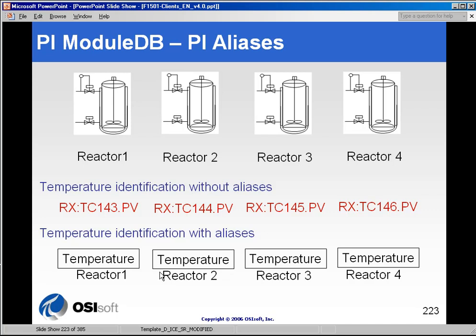Aliases get to the heart of one of the real core strengths of the module database. In the aliasing scheme, we can tie real world or common name aliases to certain devices. In this hypothetical example, I have four different reactors in my facility and they all have temperature sensors in them. Without aliasing, I would have to know what all of these temperature sending unit tag names were in order to view those process variables.